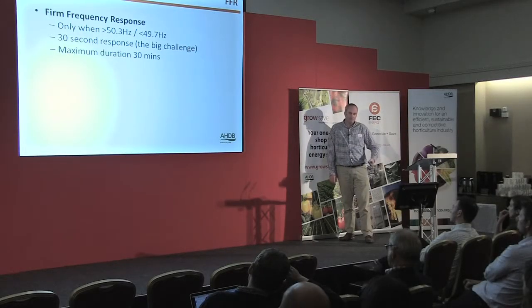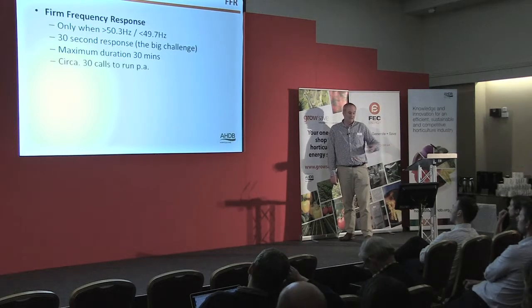Talking to some diesel engine guys, that's doable. With a bit of a smile on their face, it's like, we'll take that chip out of the engine's management system and put this one in - and it will shorten the life of the engine quite dramatically. But we're only generally being asked to run for 30 minutes max, 30 times a year. If you've got a brand new diesel engine and you reduce its lifetime by a factor of 10, if you're only running 15 hours a year, it's still got a pretty long lifetime. So you take that on the chin, the fact that you've got to be rather unsympathetic mechanically to these engines.